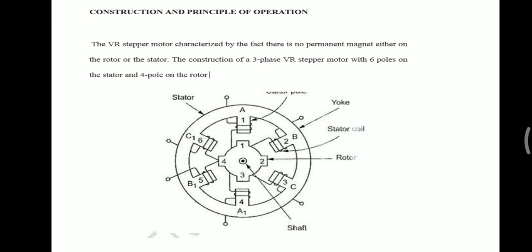The stator is made up of silicon steel stampings with inward projected even or odd numbers of poles or teeth. Each stator pole carries a field coil or excitation coil. In case of even number of poles, the excitation coils of opposite poles are connected in series such that their MMF gets added. The combination of the two coils is called phase winding.